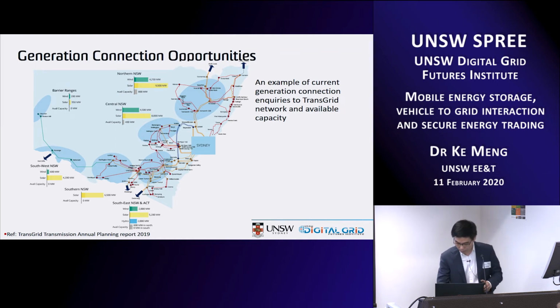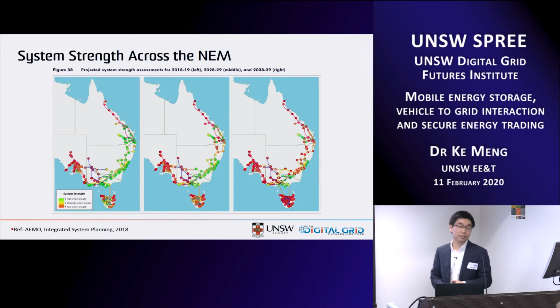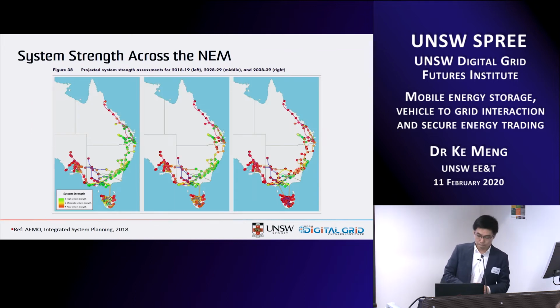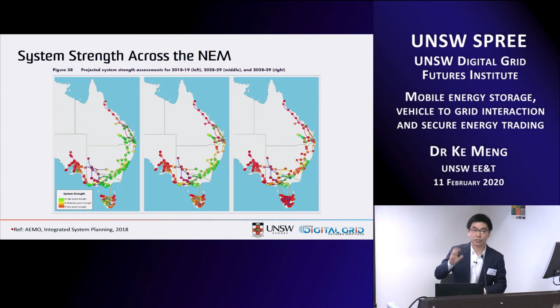One of the main issues we call system strength. Personally, I consider system strength as one of the key indicators of the system's ability to maintain stable operation when subject to a disturbance. The lower the system strength, the weaker the grid will be. So that's one of the main issues.